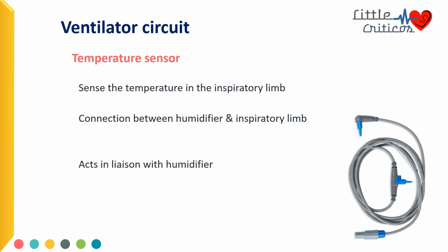Temperature sensors act by sensing the temperature in the inspiratory limb. They are usually connected between humidifier and the inspiratory limb and act in liaison with the humidifier and maintain a constant temperature throughout the inspiratory limb.